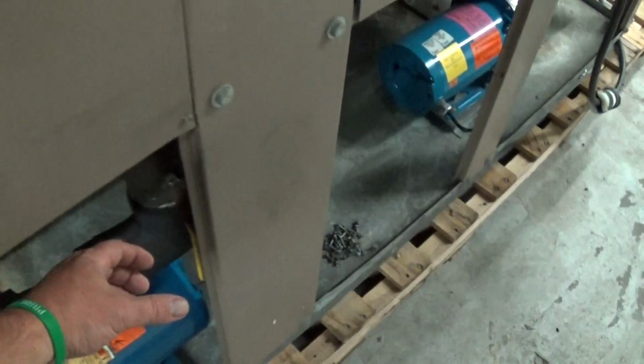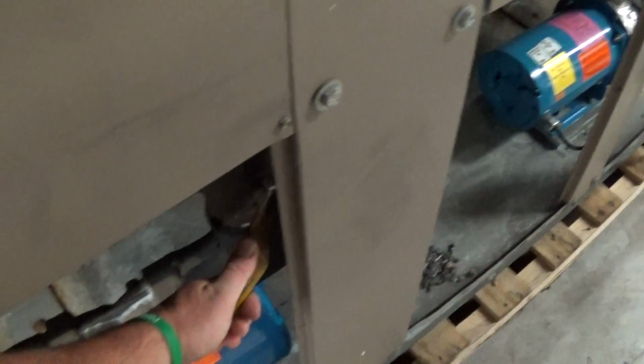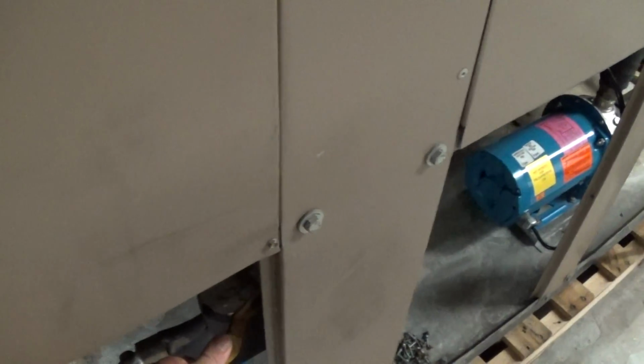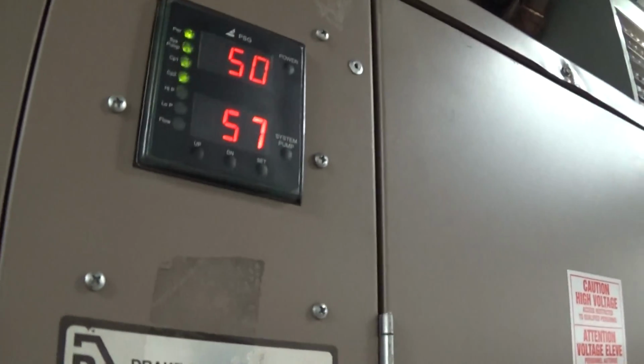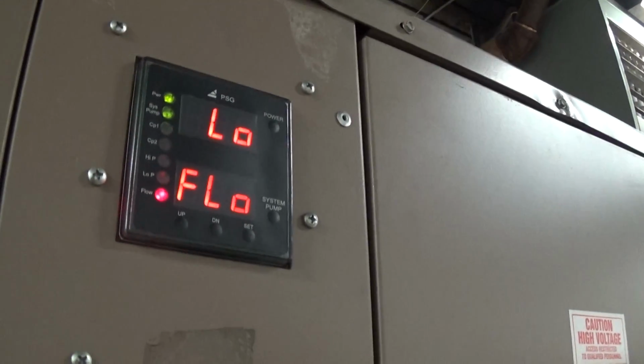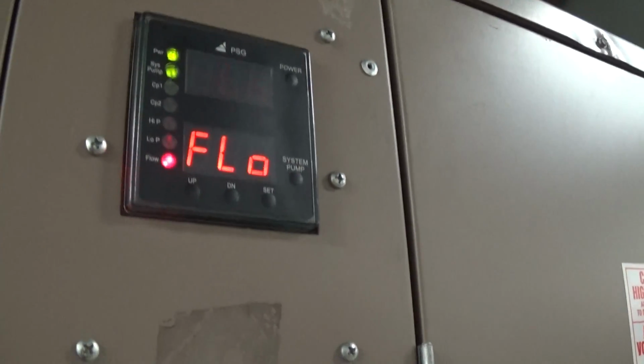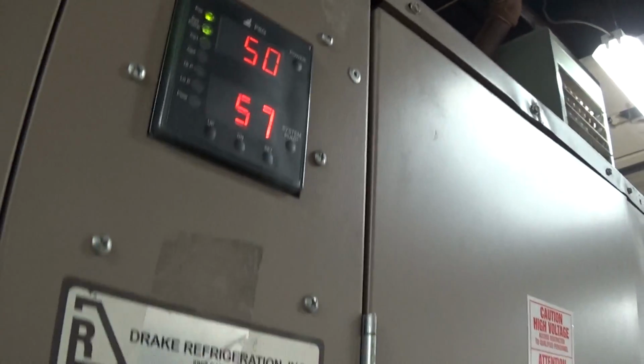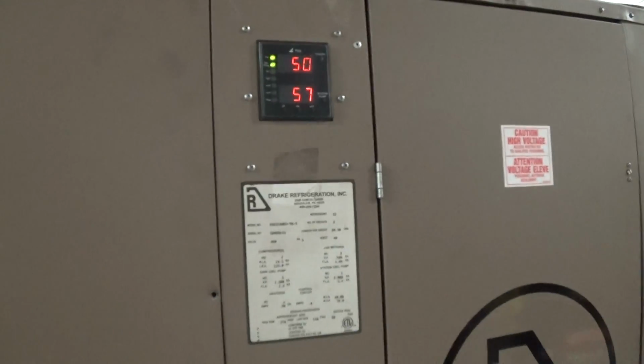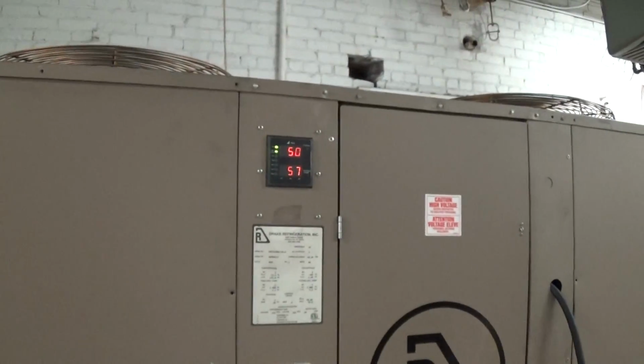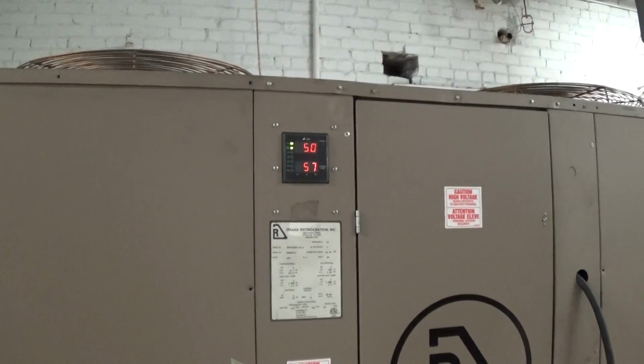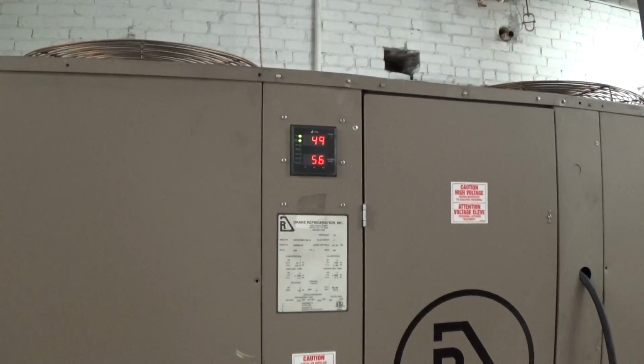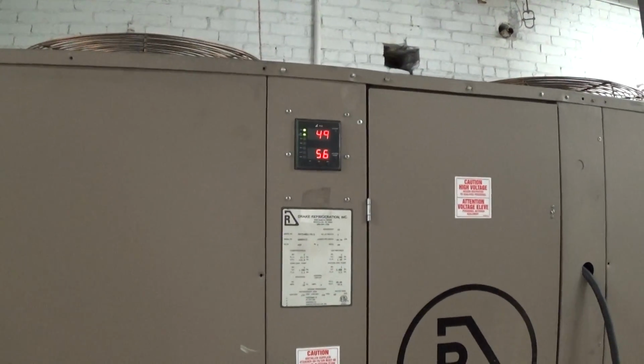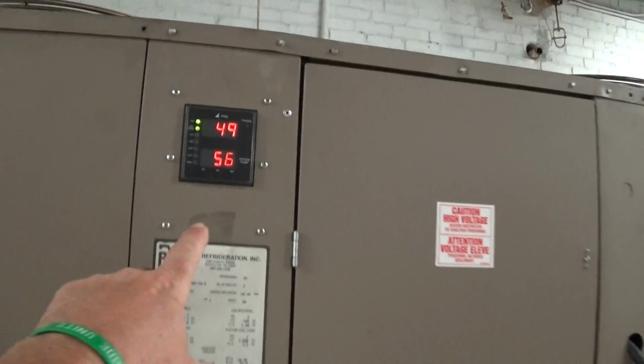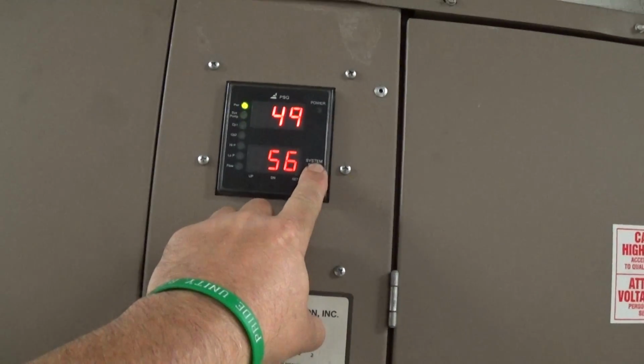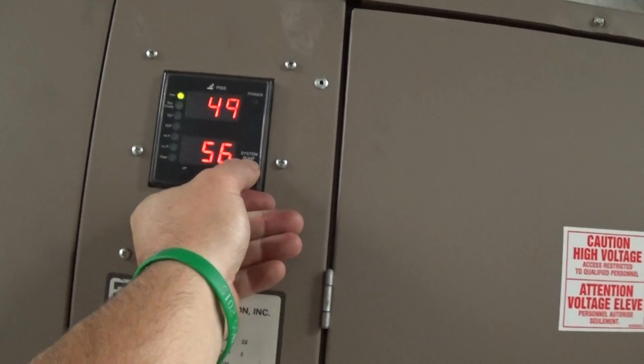So we can actually tweak the flow down here to the point where we induce an alarm there on the low flow. So I just wanted to show that to you. And now I just turn it back on. So the compressor should turn back on, or the chiller will turn back on after that alarm resets itself. The one thing you do when the system does shut down is you turn the system pump back on.